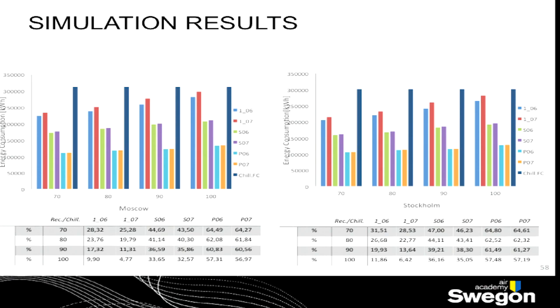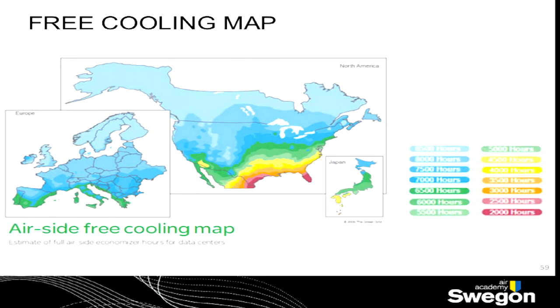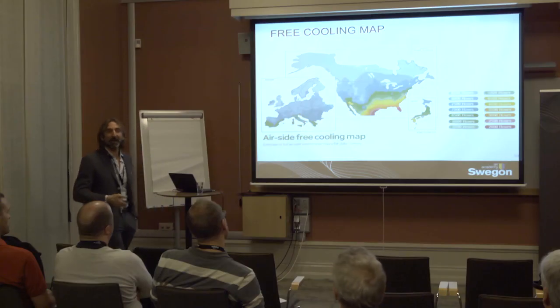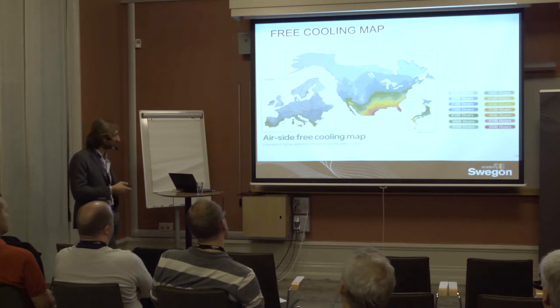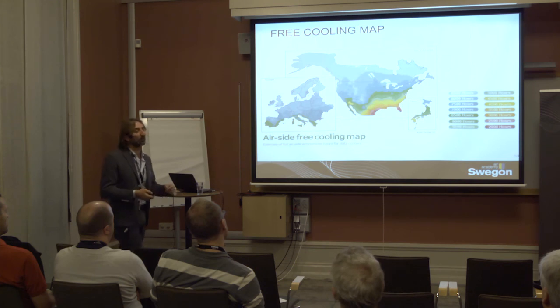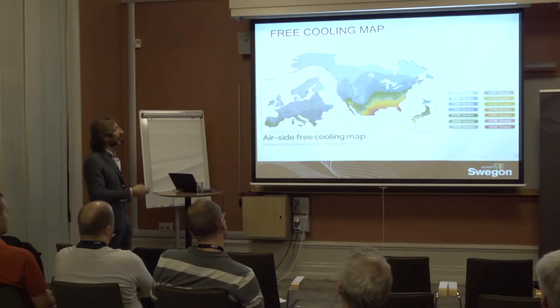In terms of free cooling map, if you consider the geographical area where we performed our analysis, we are always in situations like this one. Probably this is not a free cooling map related to an indirect free cooling system. This is related to a direct free cooling. So if you have got a direct free cooling system in the geographical area we considered, you can assume to have 7,000 to 7,500 free cooling hours per year. So more or less, let's say 80% of the total running time of the system, you can operate in direct free cooling. Of course, if you consider indirect free cooling, just due to the losses in the exchange between air and air, you lose something in terms of available hours. And this is the reason why we equip the system with an adiabatic cooling system, to increase the number of free cooling hours in a year.